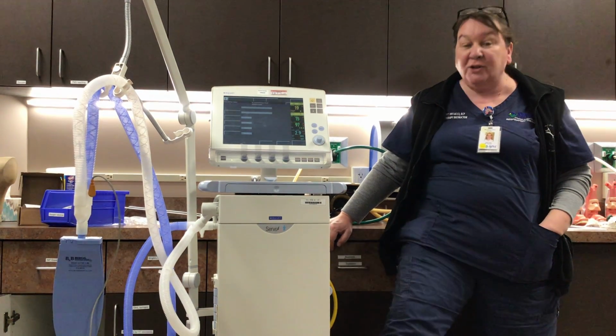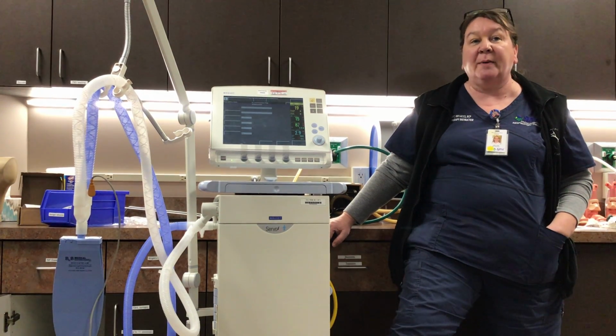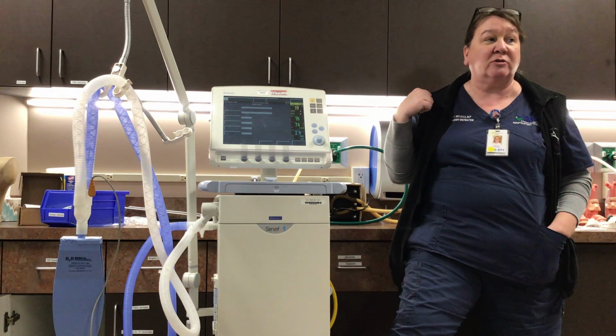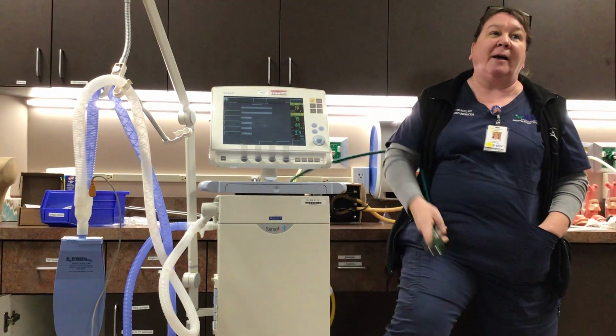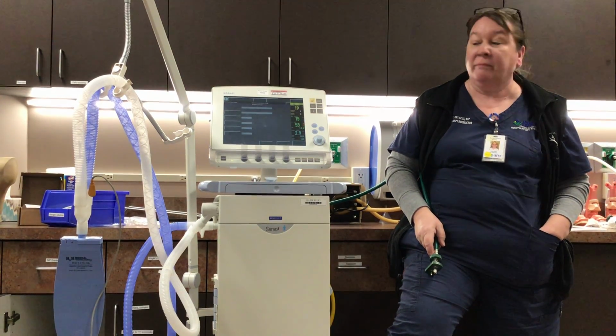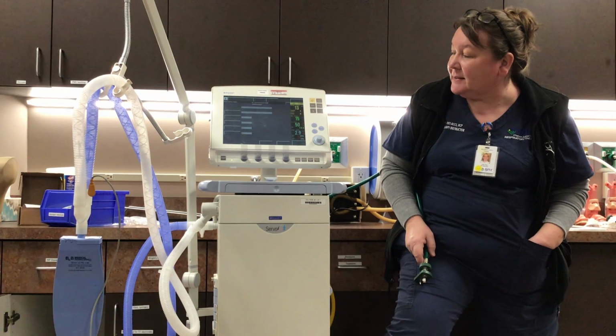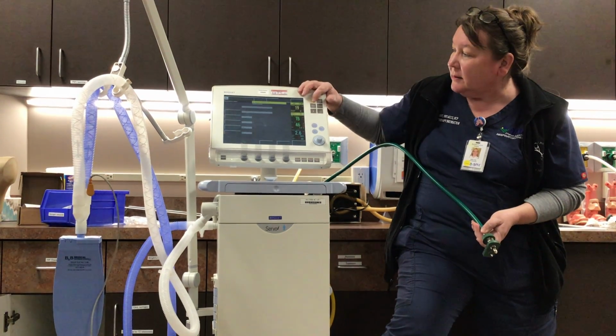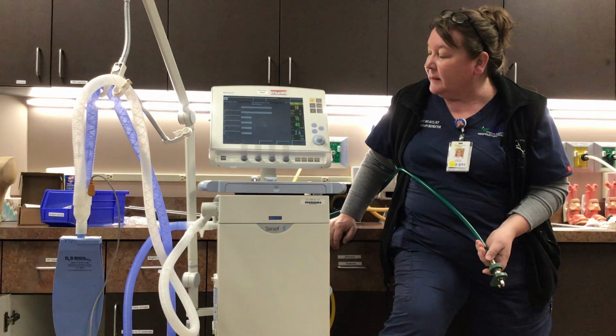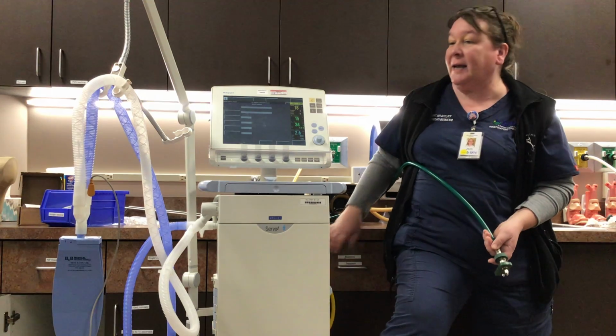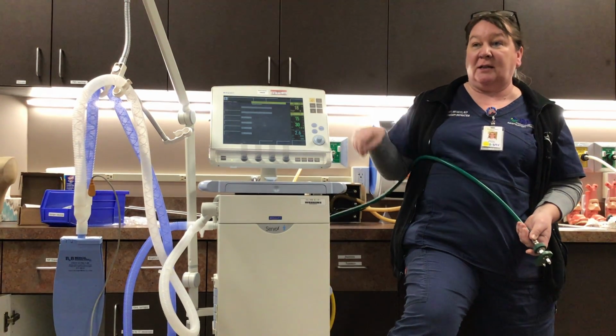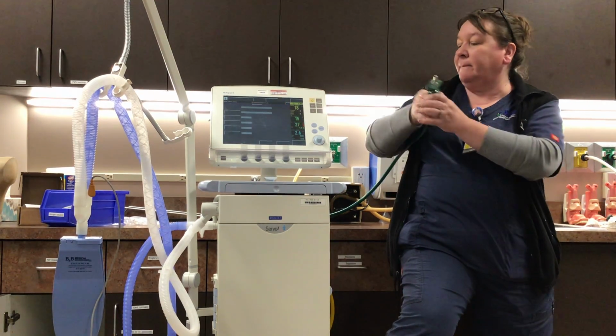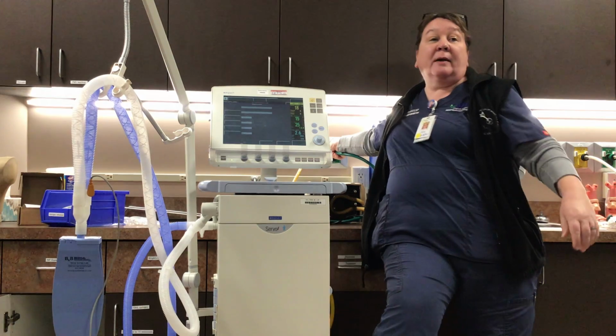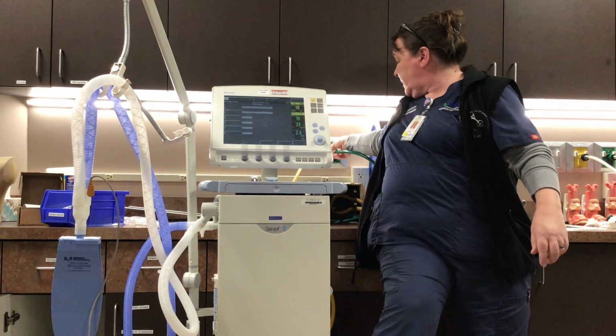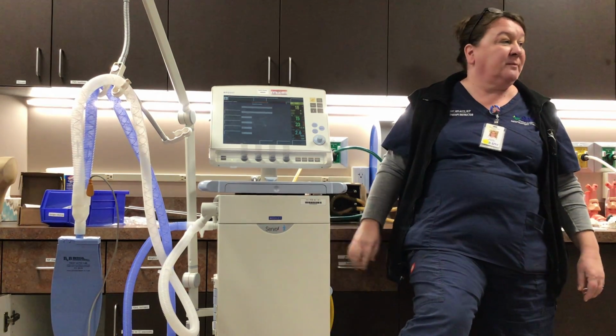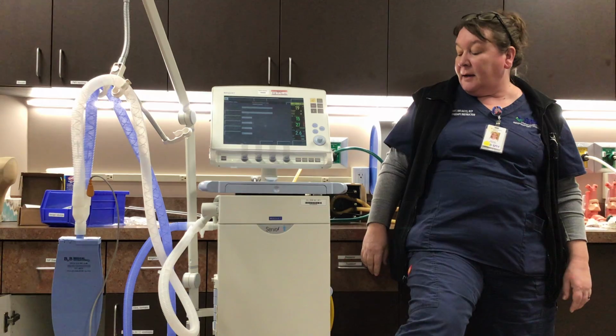And in a worst case scenario, my patient going from 40 to 100, it's not perfect, but it's better than the alternative that was gonna happen in a minute when I lose my oxygen source. And I'm gonna go from 40 to room air. And it's saying the oxygen concentration is high because it's above what I wanted it to be. Now it's saying I lost my O2 pressure, and you're gonna see it's gonna go down to room air. So again, it's functioning, it's just gonna change the FiO2 and it's gonna alarm because you're gonna have to do something. And you start wheeling around a bunch of tanks is what you're gonna do. Bringing H tanks and M tanks to people's rooms to get them by until they figure out what's going on. So that's what that is.